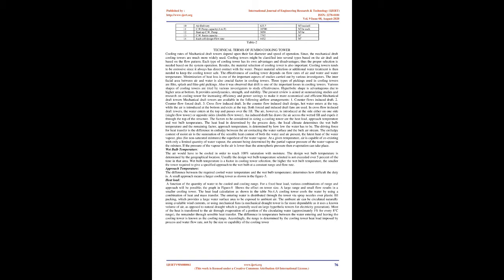Cooling rates of mechanical draft towers depend upon their fan diameter and speed of operation. Since the mechanical draft cooling towers are much more widely used, cooling towers might be classified into several types based on the air draft and based on the flow pattern. Each type of cooling tower has its own advantages and disadvantages, thus the proper selection is needed based on the system operation. Besides, the material selection of cooling tower is also important. Cooling towers tend to be corrosive since they always have direct contact with the water. Proper material selection or additional water treatment is then needed to keep the cooling tower safe.